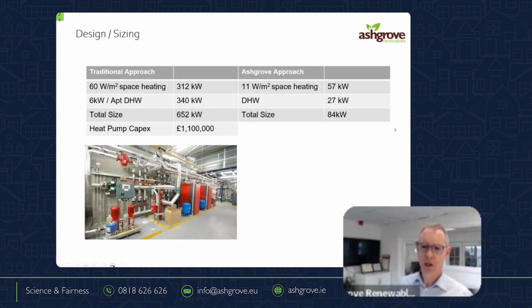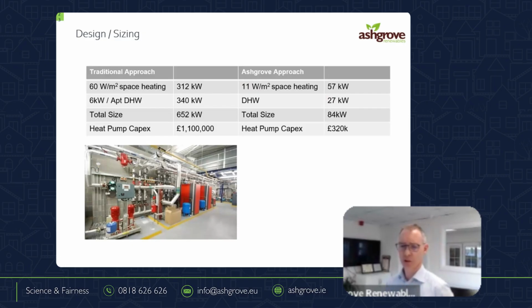We got 84. Now, what allowed this project to go ahead, for any engineers that are online here, we're sweating now at 84 kilowatts. That would have gone into 5,000 square foot houses 15 years ago, 84 kilowatts. So just to put it in context, the engineers sitting across the table from us now are literally sweating. We still put in the 600 kilowatt boiler, and it allowed them to sleep at night, and we paid 50k for that. But they save 800k.